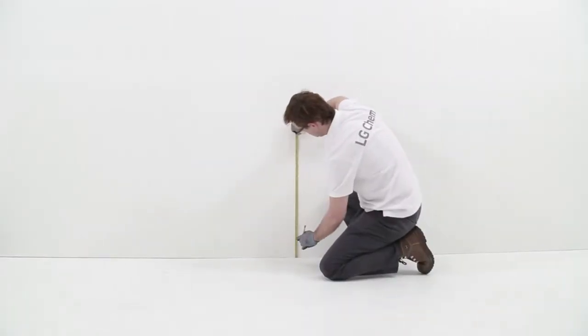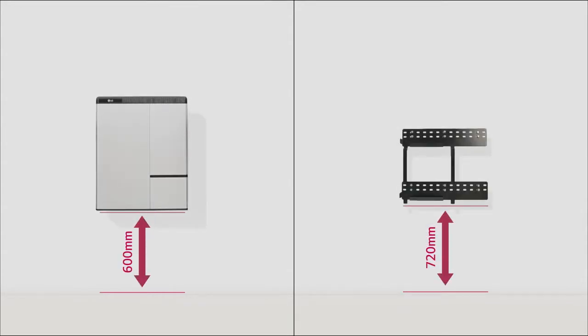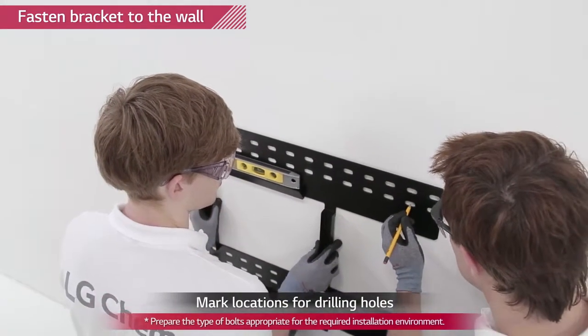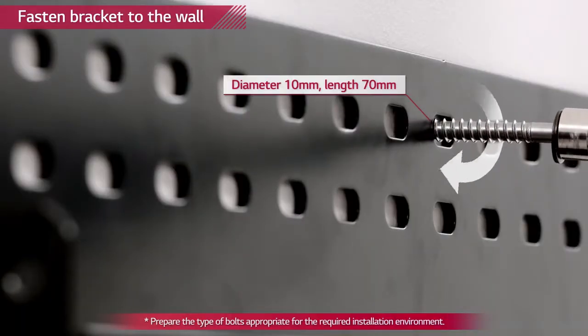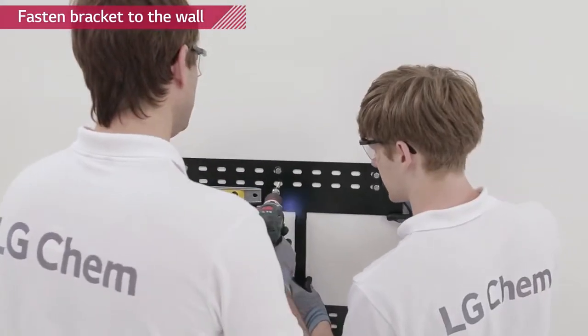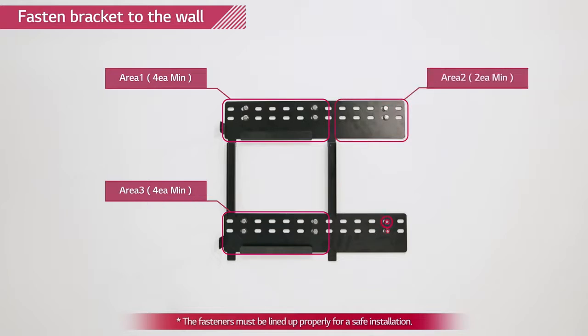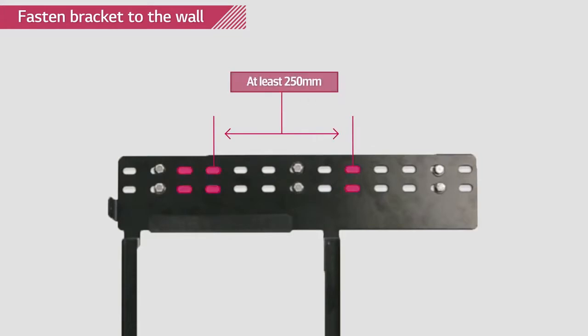First, the wall mounting bracket needs to be fixed. Please note that the RESU 7H and RESU 10H can only be wall mounted. For wall mounting bracket installation, make sure you have at least 720mm above the ground. Mark the location on the wall by placing the bracket to the wall and then drill anchor screws to the wall. Use at least 4 bolts for area 1 and 3 and at least 2 bolts for area 2 and 4. The distance between bolts in area 1 and 2 and 3 and 4 must be at least 250mm. The wall mount bracket must be leveled.